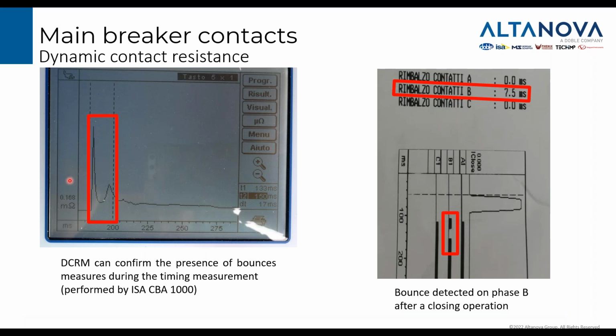Okay, this is a real measurement performed with another equipment. In this case it is a CBA 1000. This is a graph of a dynamic resistance during a close command. So the graph starts from a very high value, goes down, then there is an increase, so there is a second peak in the measurement, and this is clearly something that indicates a problem in the circuit breaker. The same information is confirmed by a standard time test. It's clear here that there is a bounce. So this hole is correlated to this peak here. So the two measurements are confirming the problem somewhere in phase B.